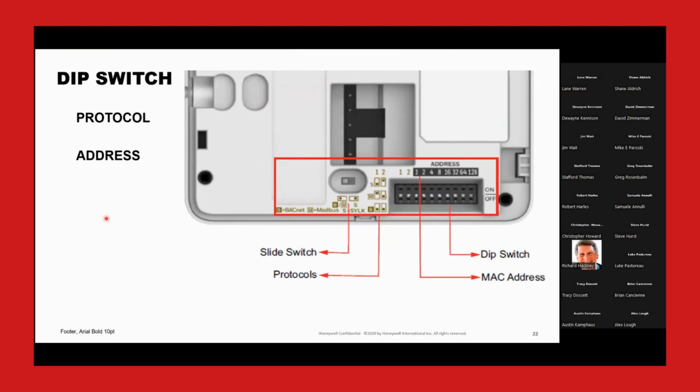Yeah, if you bring it in through a Modbus port on a Spyder 5 or 7, the answer is no, because it's just like a slave device. It's just something downstream. So if you're talking Modbus to a Spyder 7 or an optimizer fan coil unit controller or unitary controller, you could bring in 40, 50 objects from this controller into the Spyder. In fact, you'll see that I've got one running behind me, and I'll show you that live in a minute. And none of that counts against your Jace point count. The only things that count against your Niagara point count are the BACnet objects that you bring over.